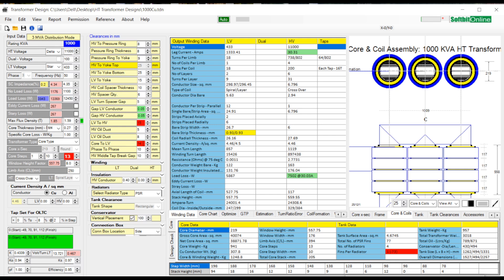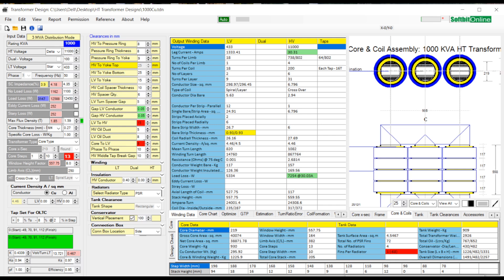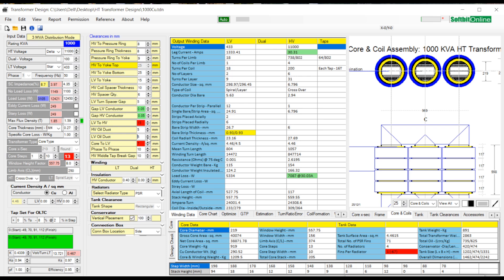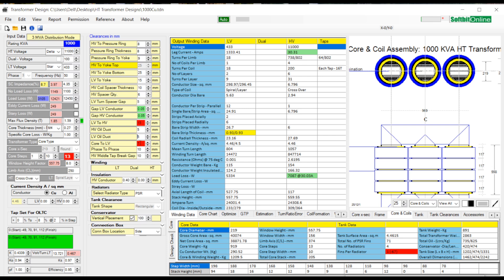For heat dissipation of windings and coils to oil, the windings are split into two sections. The gap between the two sections is called oil duct as oil is filled in these gaps. This gap for oil duct is generated while making the coil. This can be had only in one winding, HV or LV, or in both the windings. Next comes core to LV clearance.